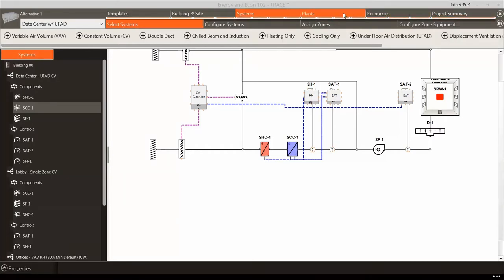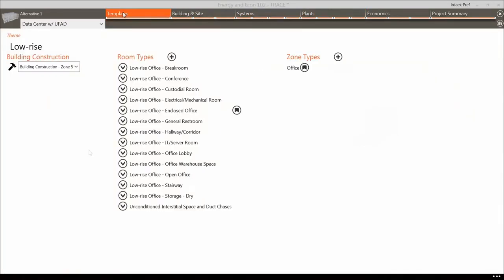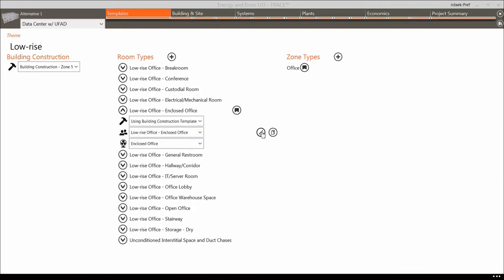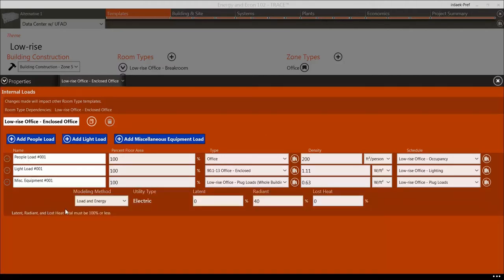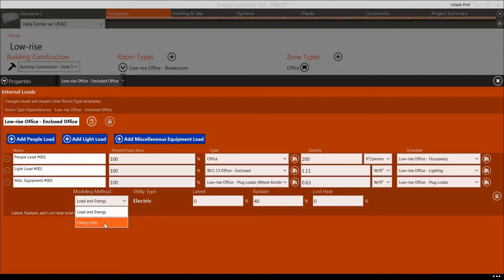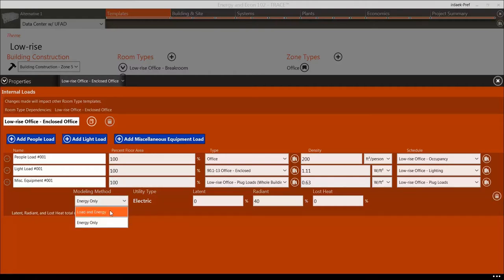Let's take a closer look at the modeling method for miscellaneous loads that can be applied using the templates. Open the Enclosed Office Internal Loads template and view a miscellaneous load. This load now has an energy-only selection under the modeling method dropdown. By selecting the energy-only field, TRACE 3D Plus will not add this internal load to the space as a load; rather, it just spins the utility meter type referenced from the library. This is one field you may want to modify when converting from a load design to an energy simulation.